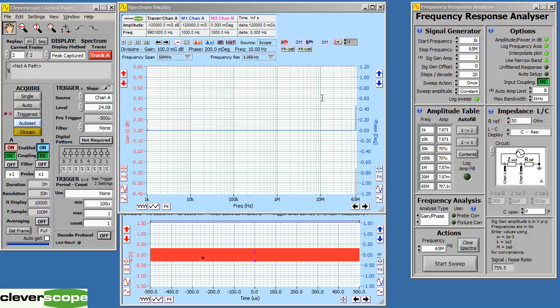Right, as for the standard probe calibration, with the BNC probe calibration we need to set the frequency range. We've set it to 1 kHz to 65 MHz, the upper frequency limit for the FRA. We set a SIGGEN amplitude of 2 volts, and again we're going for 20 steps per decade. We're going to measure gain phase without any probe correction just to see what we've got.